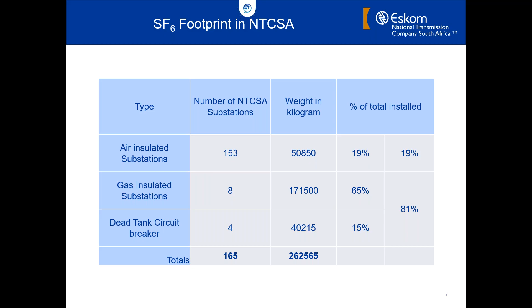On the GIS side, we've got 8 substations, contributing to 65% of all SF6 used in Eskom. Dead tank circuit breakers, as mentioned, are at 4 stations, contributing 15%. That means Eskom is sitting with 262 tons of SF6 currently as a footprint, out of which 81% is lying in the bin of the GIS as well as the dead tank circuit breakers.